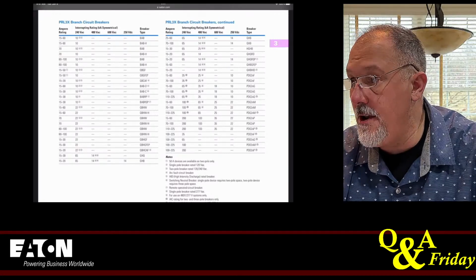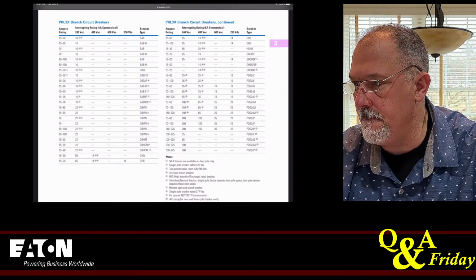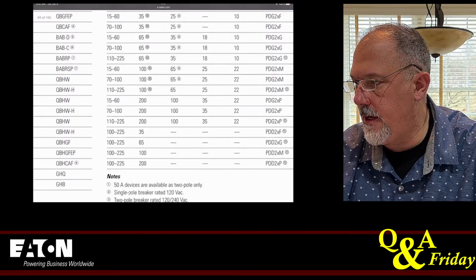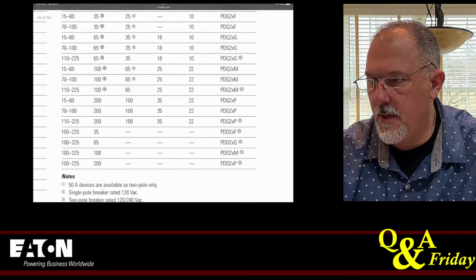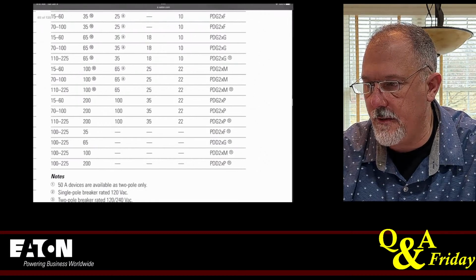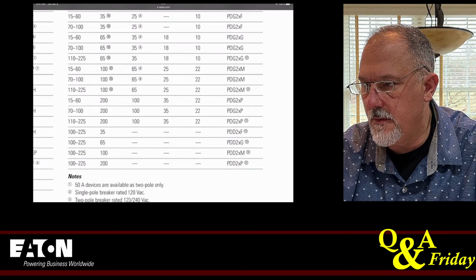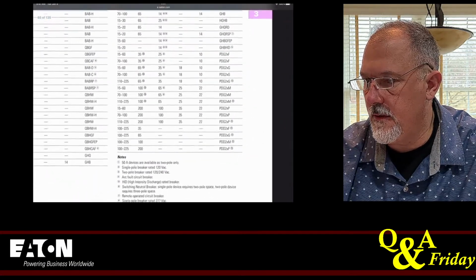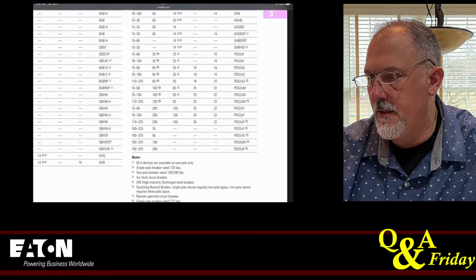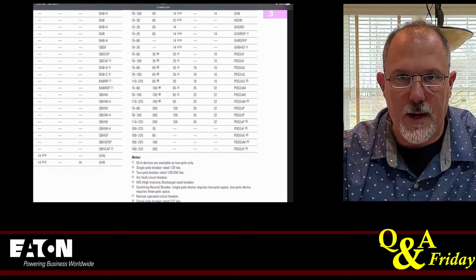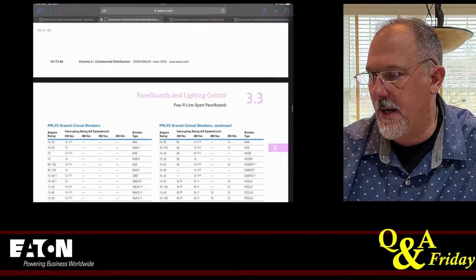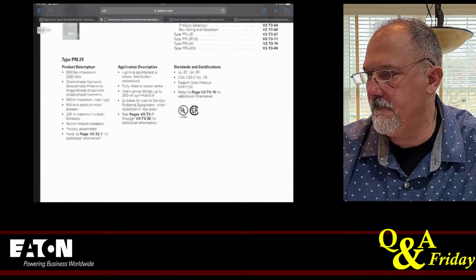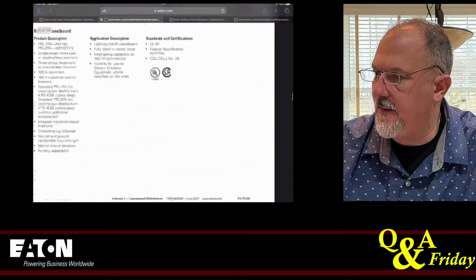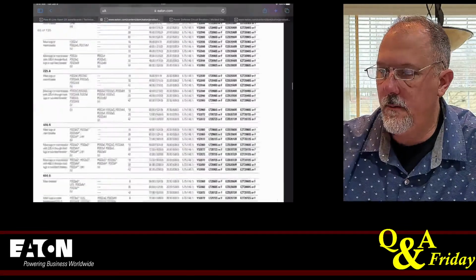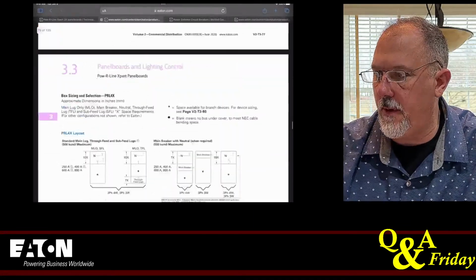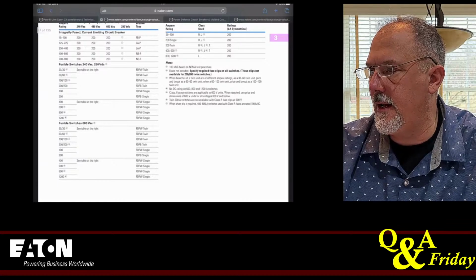So I can go up to a 200 amp right here with a PDG2 plus P. So I can go up to 225 right here. So 110 to 225, 200,000 amp interrupting rating. So I can go to 225, 225. So I could put that Powerline Expert panel board upstream. So you see what I'm saying? You have to pick what's the equipment that you have.